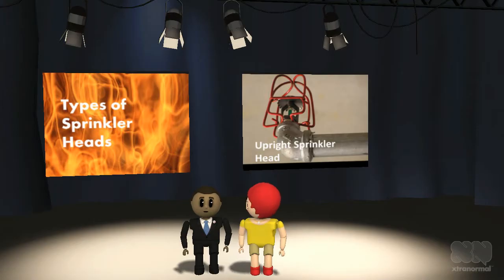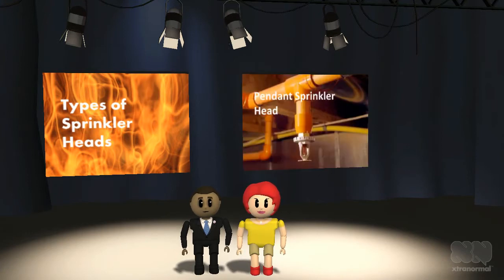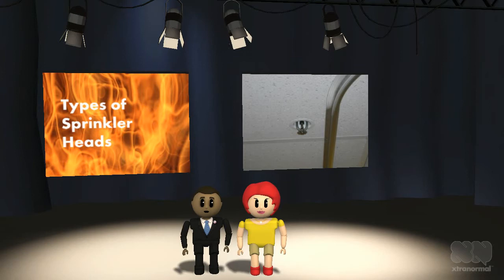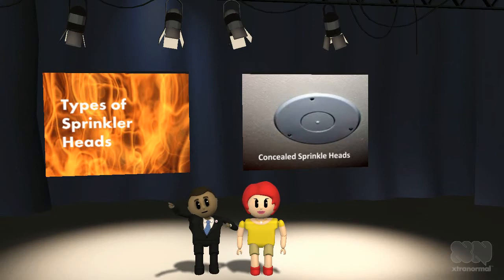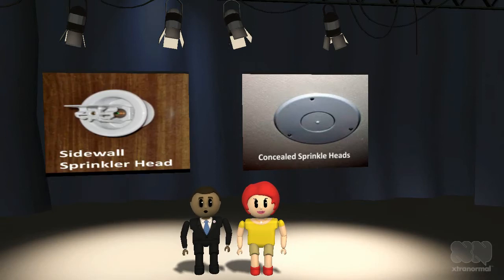Let's talk now about the different kinds of sprinkler heads. The upright sprinkler heads sit on top of exposed supply piping. Pendant heads hang below piping. Pendant heads may be recessed, with part of the sprinkler body concealed above suspended ceilings and the deflector located below the ceiling. Flush heads have only the heat-detecting element below a ceiling. Concealed heads are located entirely above a ceiling, with a cover plate that falls away in the fire. And last but not least, we have the side-wall sprinkler heads, which are usually located adjacent to one wall of small rooms, as in hotels or apartments.